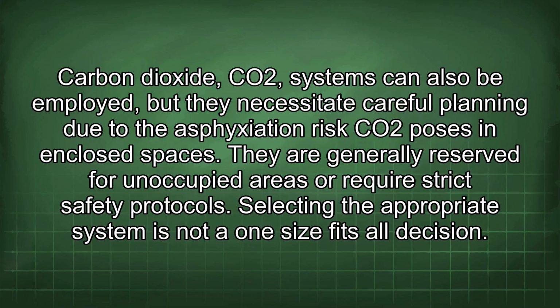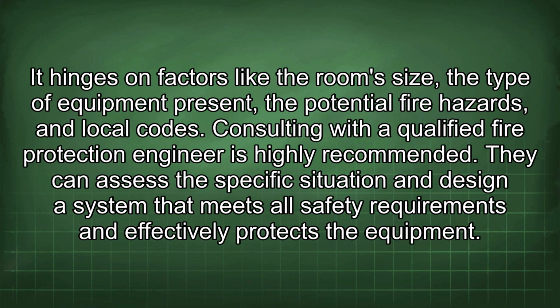Selecting the appropriate system is not a one-size-fits-all decision. It hinges on factors like the room's size, the type of equipment present, the potential fire hazards, and local codes. Consulting with a qualified fire protection engineer is highly recommended. They can assess the specific situation and design a system that meets all safety requirements and effectively protects the equipment.